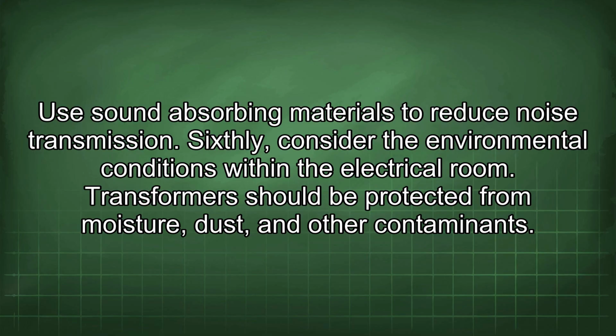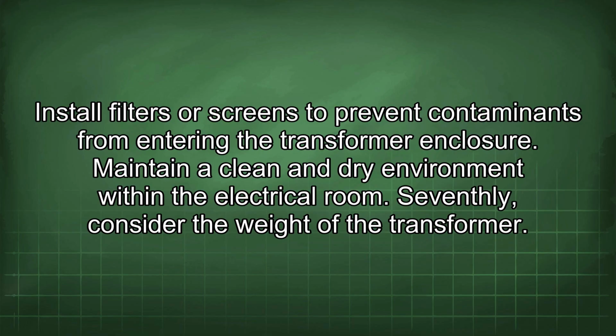Transformers should be protected from moisture, dust, and other contaminants. Install filters or screens to prevent contaminants from entering the transformer enclosure. Maintain a clean and dry environment within the electrical room. Seventhly, consider the weight of the transformer.